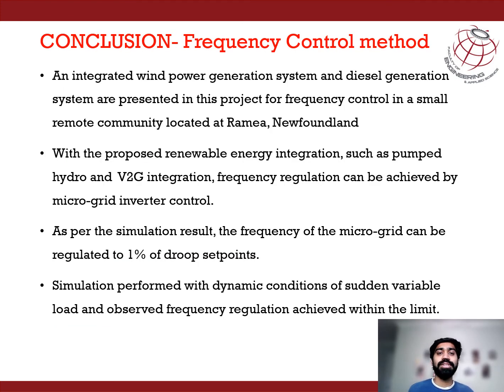To conclude the frequency control part of this project, we have simulated the frequency control effect with the Ramea Island existing energy generation system and the proposed energy generation system, such as pumped hydro, vehicle to grid integration, and wave energy, in MATLAB. And we can observe that the frequency control can be done with the droop control method, and the frequency deviation can be kept within the 1% droop set point. The simulation was done with dynamic load conditions as well, and the frequency was observed within the limit.